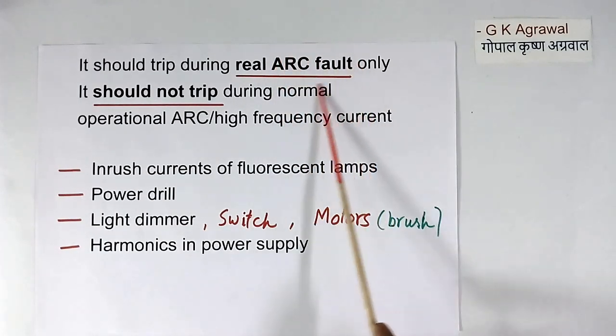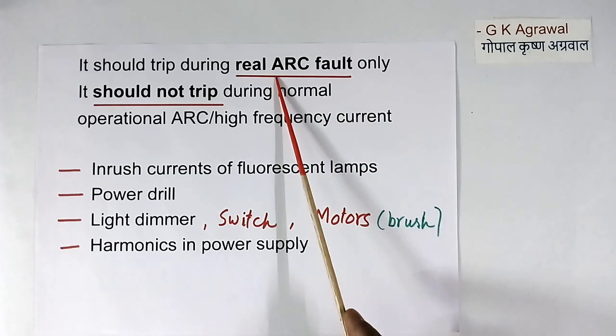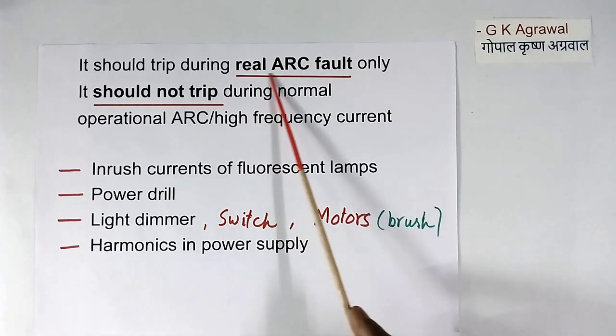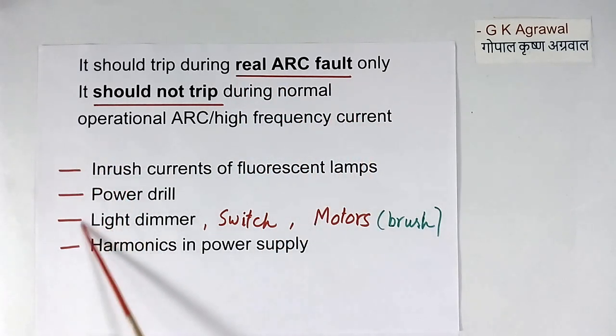Now this arc fault generates high frequency current in the wire. But high frequency current is generated from so many things, like inrush current in lamps, power drill, light dimmer, switch, brush motors, harmonics in power supply. All these generate harmonics. All these generate high frequency current in the wire. Then controller should differentiate between them.